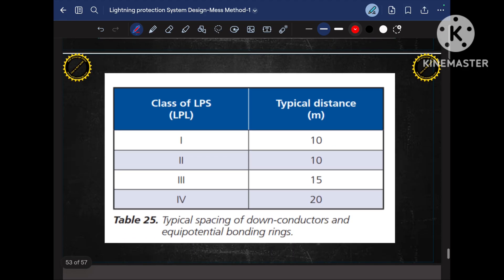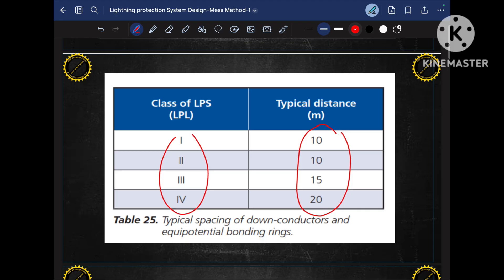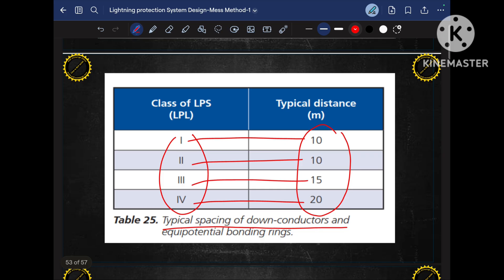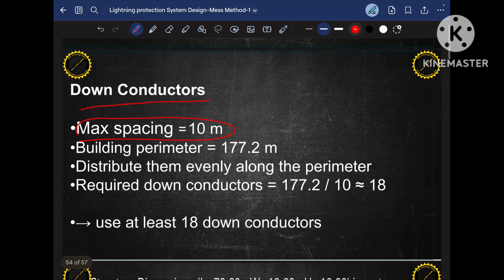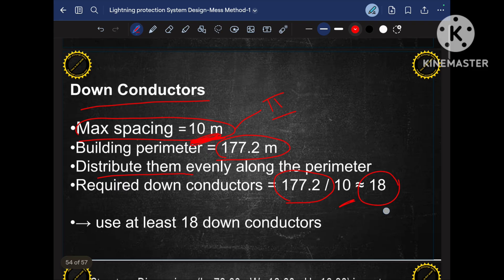As per IEC standard, different classes have different down conductor spacing. For class 1 and class 2 it is 10 meters, for class 3 it is 15 meters, and for class 4 it is 20 meters. Since our selected class is class 2, the required down conductor spacing is 10 meters. The perimeter of the building is 177.2 meters — if there is a minor mathematical error please ignore it, I am focusing on the concept. Dividing the perimeter by 10 and distributing evenly, we get a total of 18 down conductors required for our project.